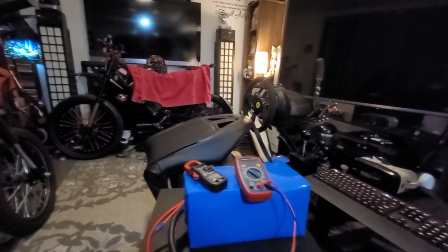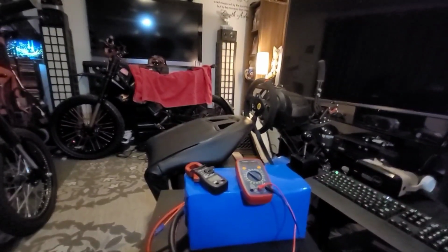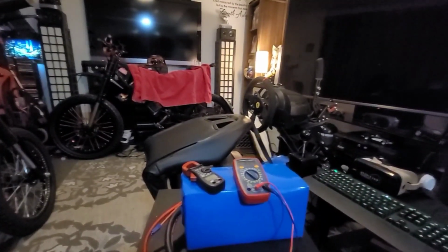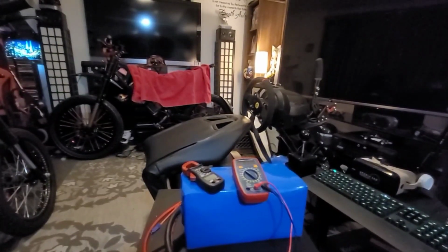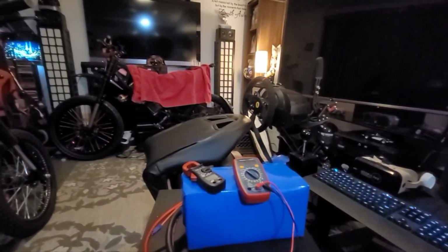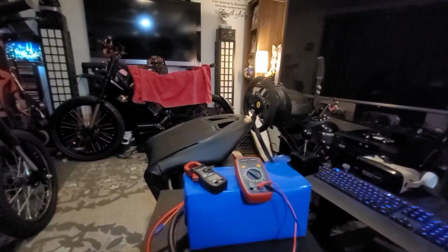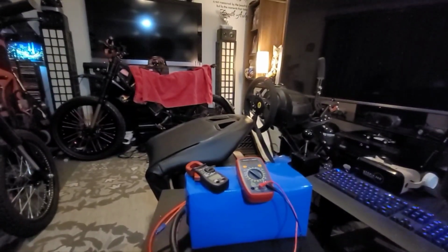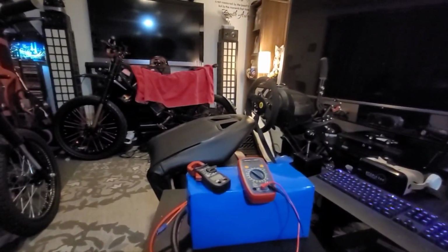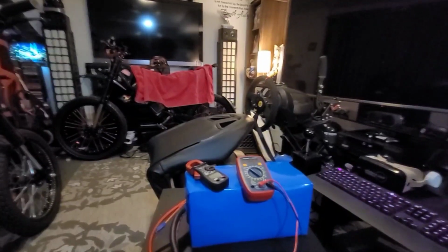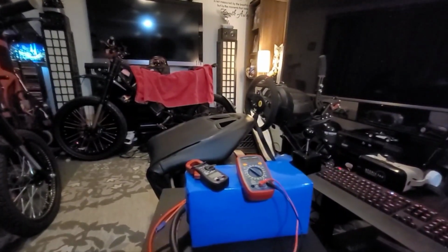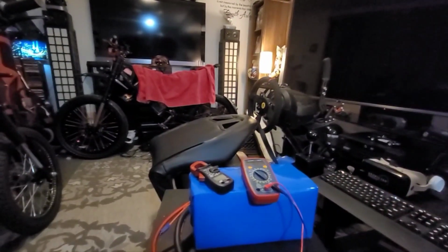So if you have a Sabvoton 72150 set to 350 phase amps, 150 DC amps, and you bypass that 80 amp BMS, you will not be shortening that battery's life, because that's what the battery is designed to do.